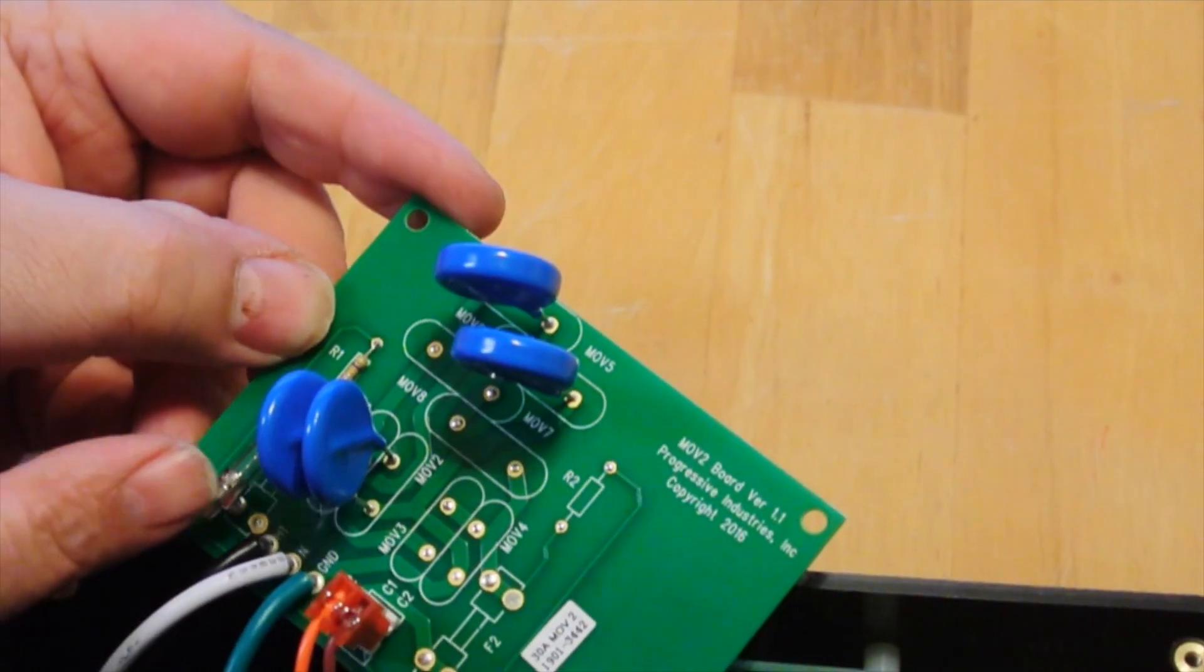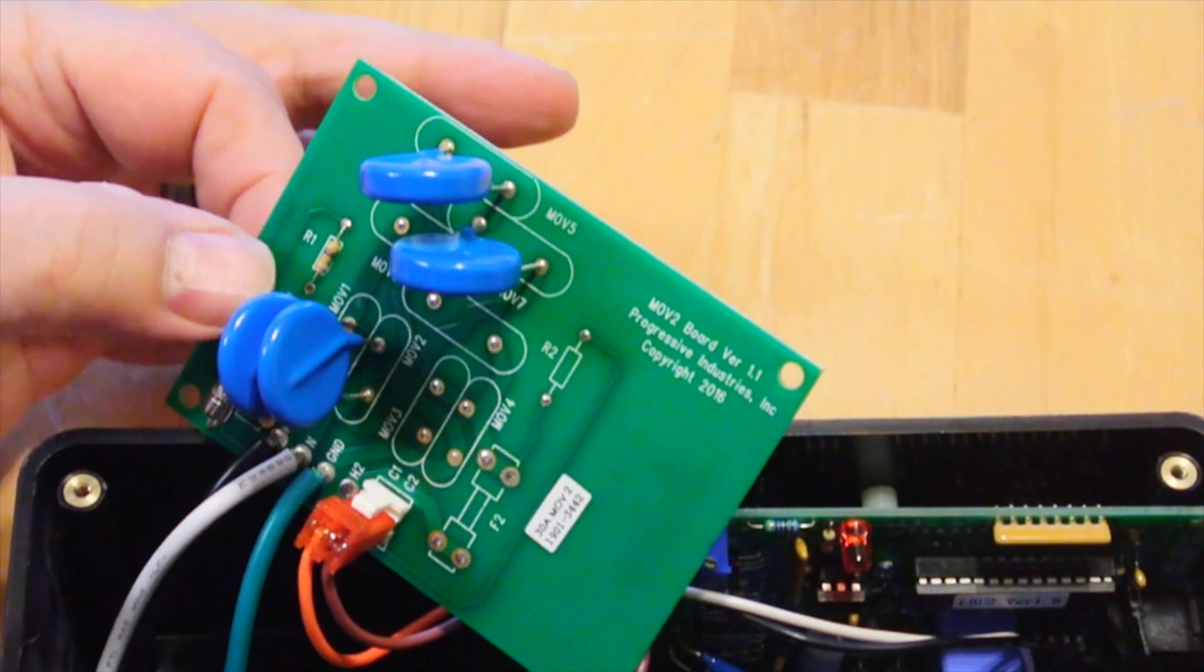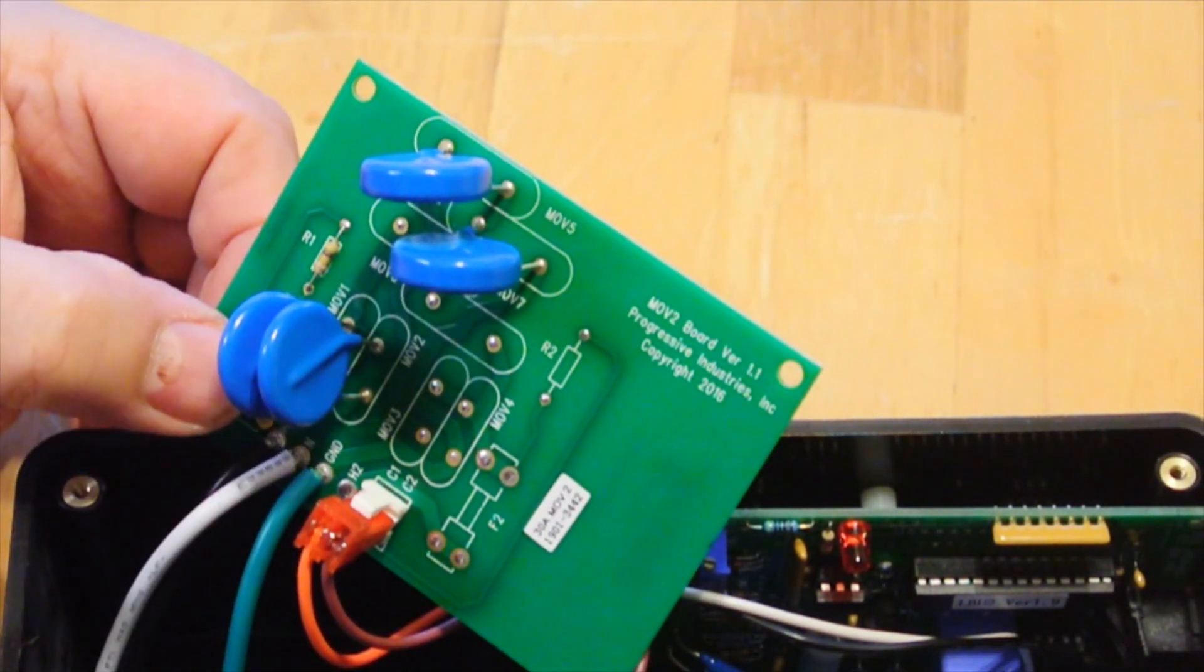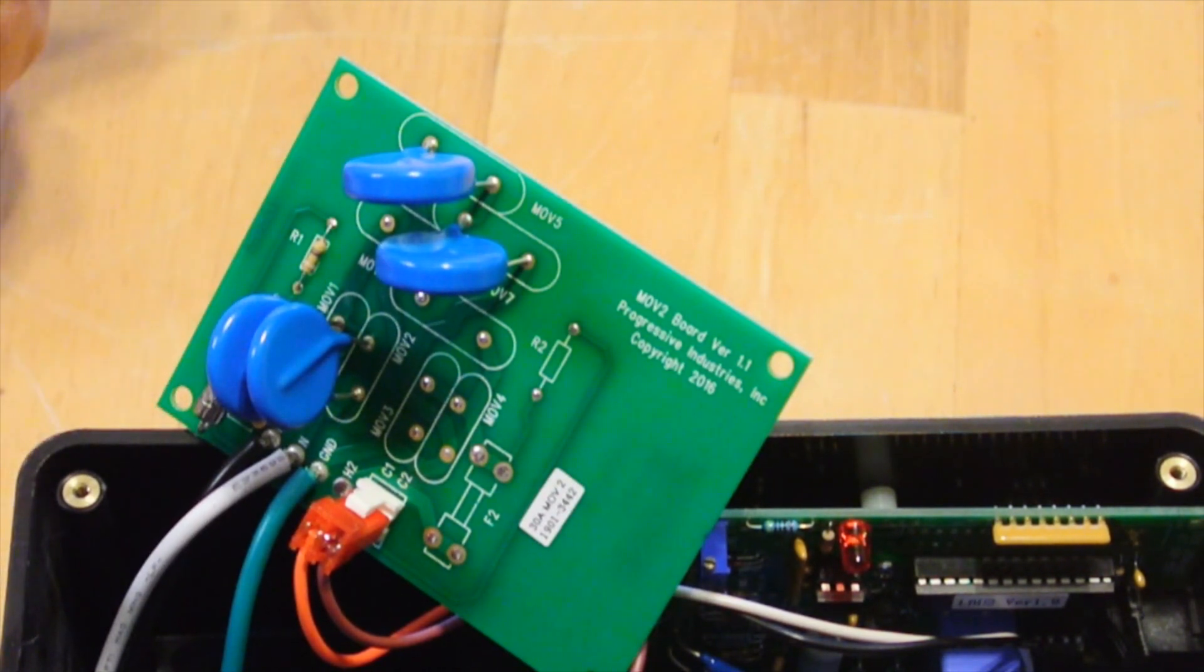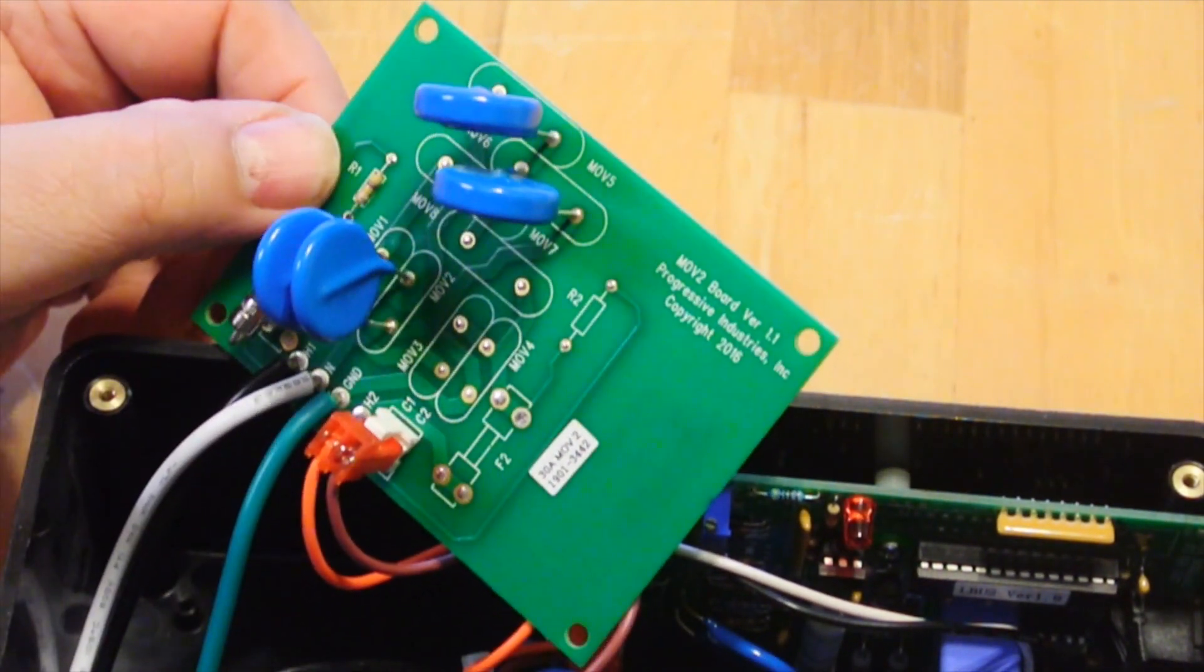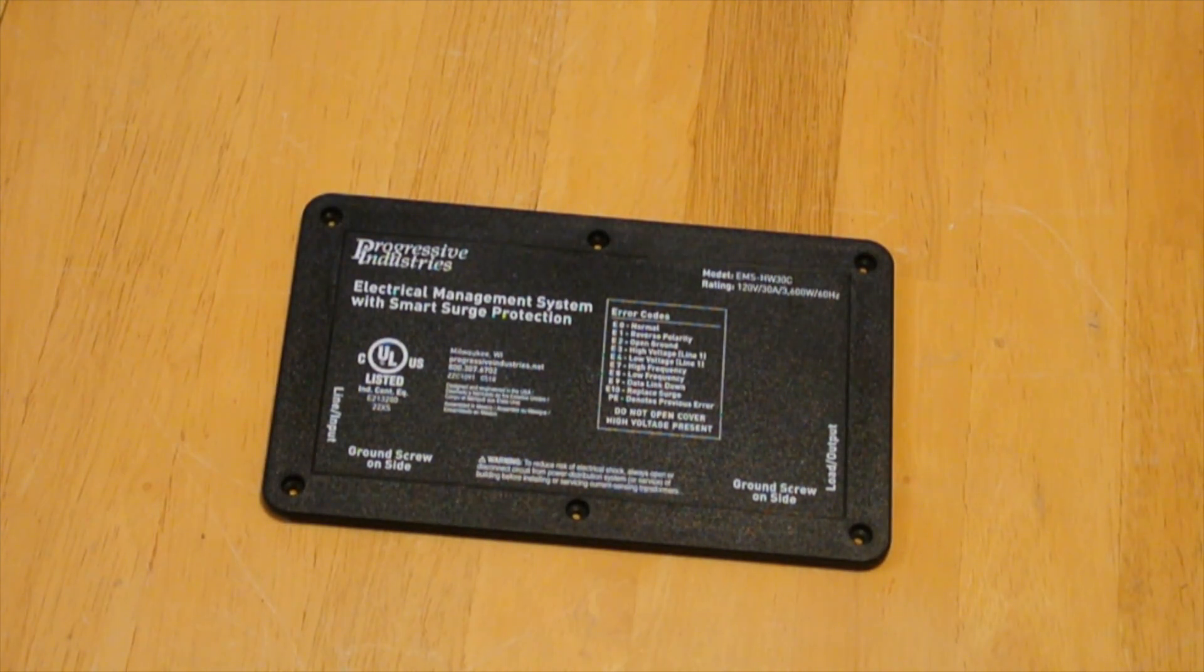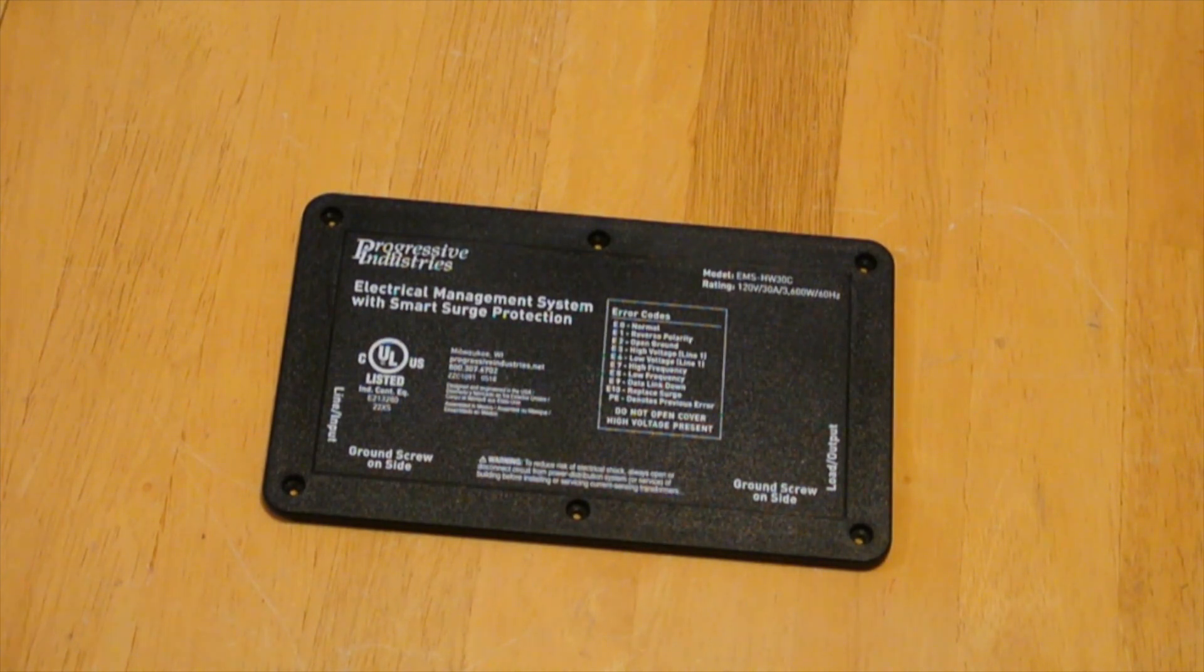And here you can see that we also have a fuse on the MOV board, and this board is also replaceable. At some point, these MOVs will fail, blow the fuse. And if you had a surge protector, you're going to throw it away. However, with an EMS system, you can get a new board from the manufacturer. And unlike the surge suppressor we saw previously, this device is UL rated for Canada and the US.